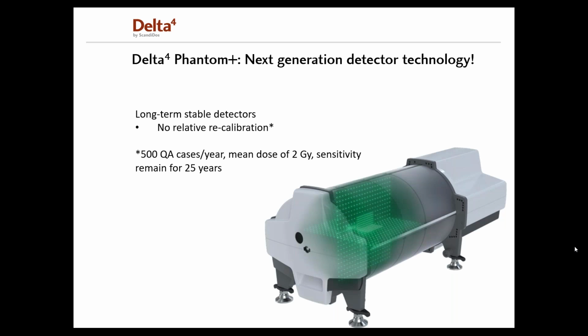The Delta4 Phantom Plus uses new highly stable detectors with a sensitivity decrease of only 0.04% per kilogray. So it needs more than 25 kilograys to lose 1% sensitivity. So if you do a lot of QA, say around 500 QA cases per year, with a mean fraction dose of 2 gray, that is 1 kilogray per year, the detectors would remain within 1% for 25 years. So the need for recalibration of the detectors is reduced to once every 25 years. And 25 years is a long time. It's actually longer than the lifetime of the system itself. So therefore, there would be no need to perform relative recalibration nor directional recalibration at the clinic.